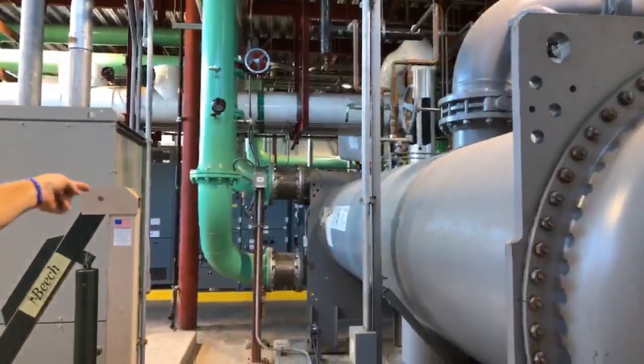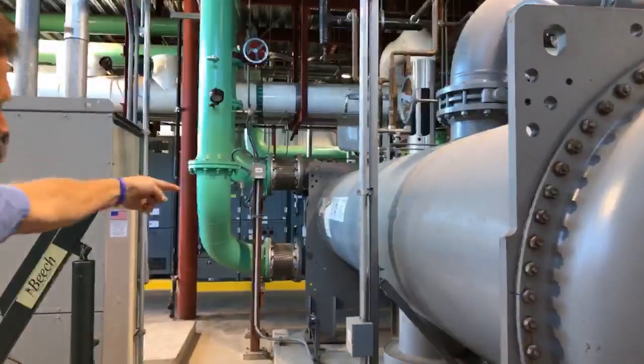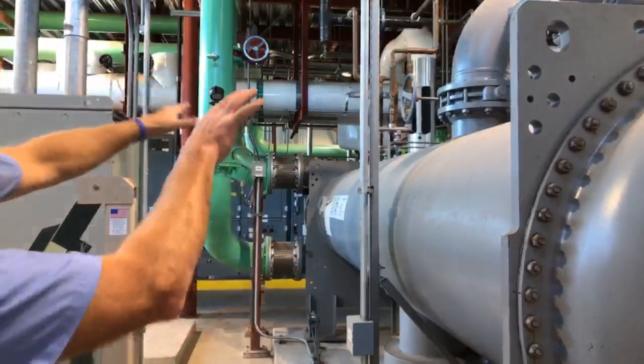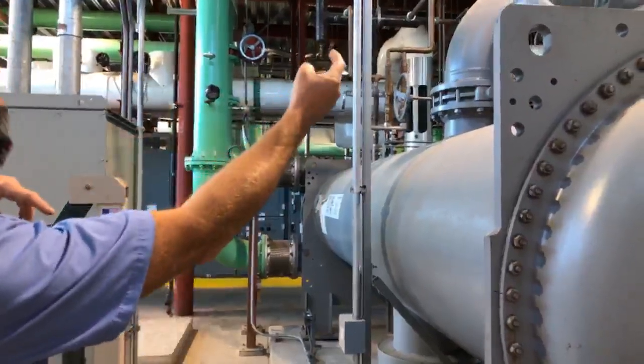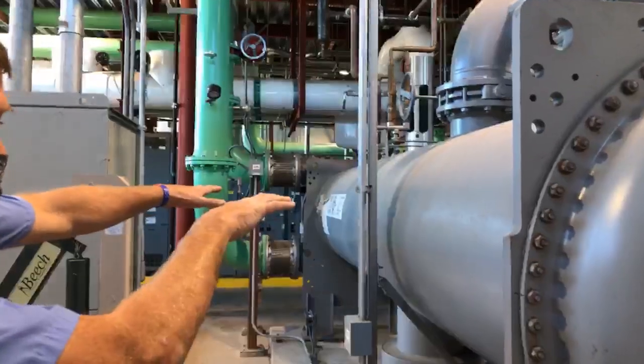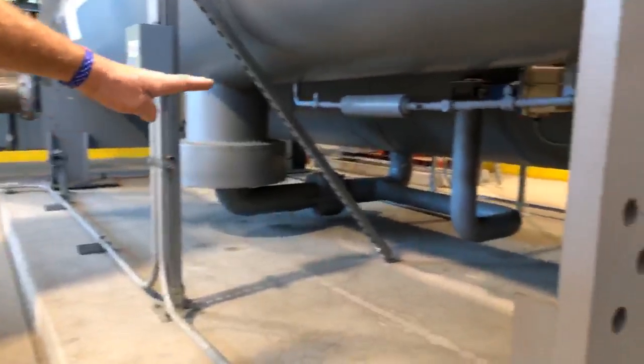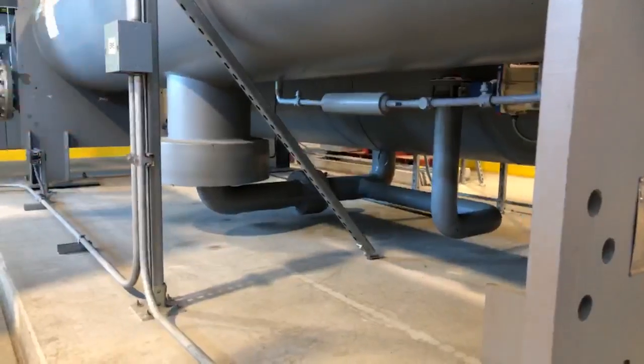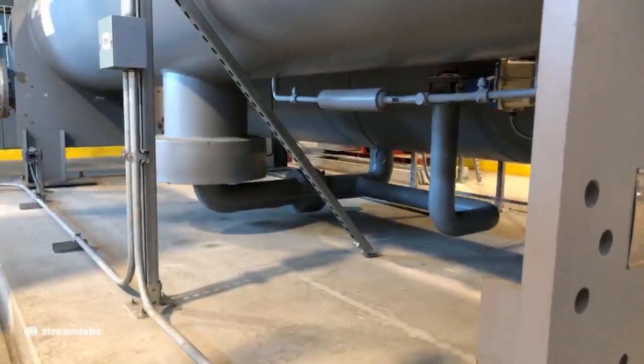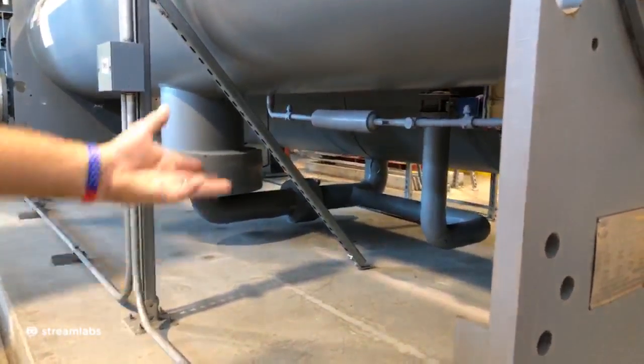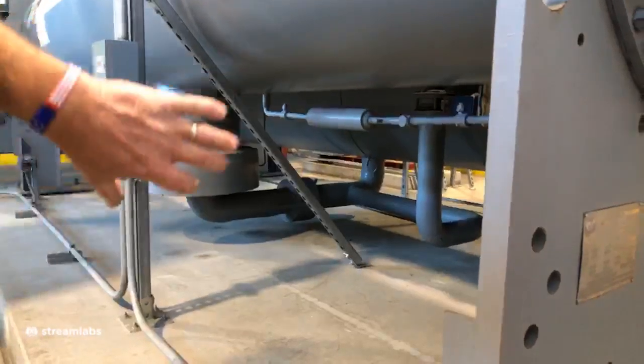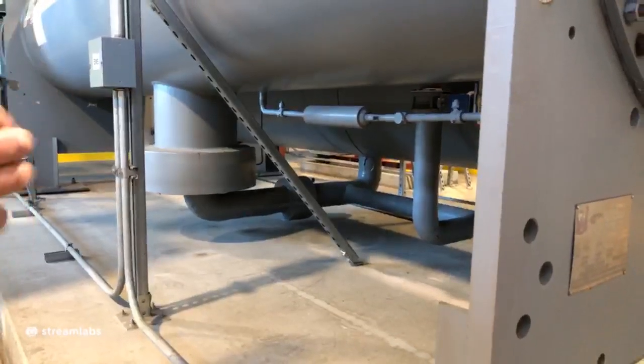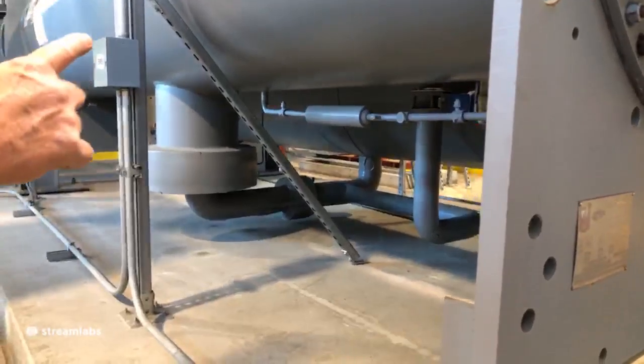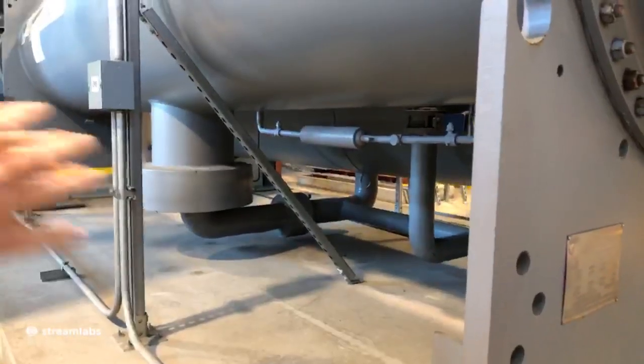Well, the green is the condensing water flowing from the cooling towers, 73 degrees in and back out, and it condenses that vaporized refrigerant back into a liquid. And then down underneath, the liquid flows back through a set of control valves, maintaining levels in both. And then the liquid refrigerant gets sucked into the bottom of the evaporator where the compressor is pulling a vacuum, so when the refrigerant gets in there, it flashes.